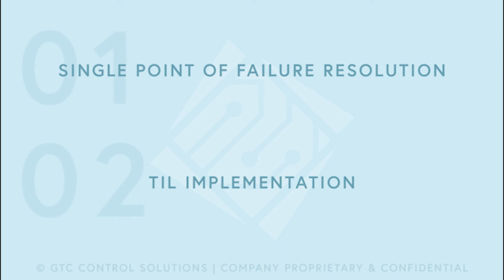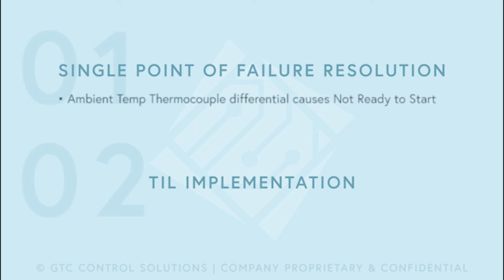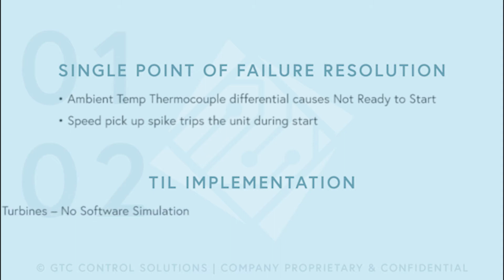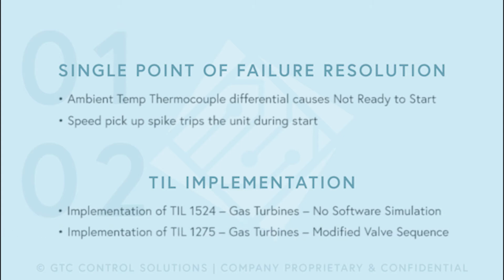We see again the items to discuss. The ambient temperature thermocouple differential that causes a not ready to start. Then the speed pickup that spikes and trips the unit during start, and then the TIL implementations, TIL 1524 and TIL 1275. And this is the end of this introduction. Now we're going into the specific discussion of each item. We're going to talk about the single point of failures and the TILs.